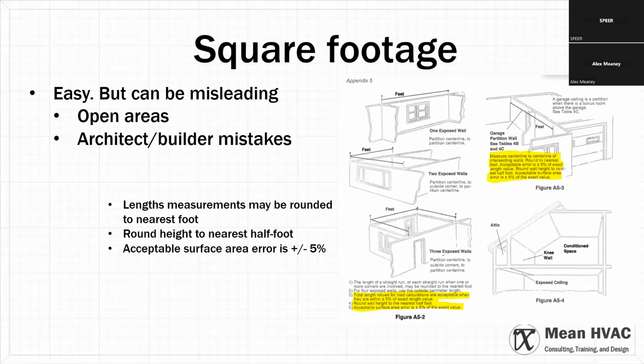That's why it's a terrible tool for sizing a system, right? How many square feet per ton? Because it has very little to do with the load. But when you're trying to check somebody's work without redoing it, it is a very good place to start. I have seen too many people focus very laser-like on square footage and make it the main pass or fail of the process.